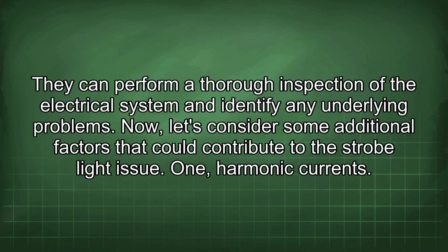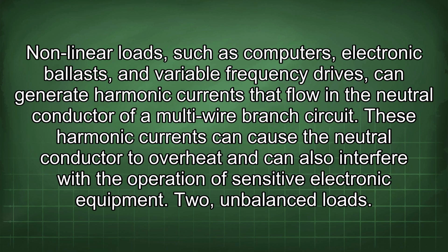Now, let's consider some additional factors that could contribute to the strobe light issue. 1. Harmonic currents. Nonlinear loads such as computers, electronic ballasts, and variable frequency drives can generate harmonic currents that flow in the neutral conductor of a multi-wire branch circuit. These harmonic currents can cause the neutral conductor to overheat and can also interfere with the operation of sensitive electronic equipment.